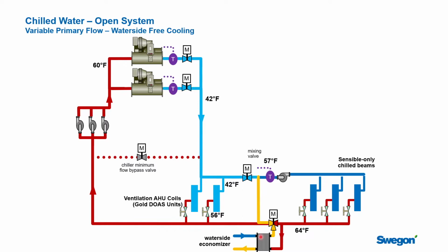And so now what we can do is use our cooling tower plant over here and speed up the fans to cool it down so that we can make 57 degree water to supply to the building. And that 57 degree water is really nice. I mean, that's a lot warmer than most chiller plant requirements because we only have to do sensible cooling out here. It's going to increase the number of bin hours, the degree days where you could service the building with waterside free cooling, right? Because that's a lot warmer. I'm going to get a lot more hours, wherever your city is, that would allow you to use cooling tower water to achieve 57 degrees.